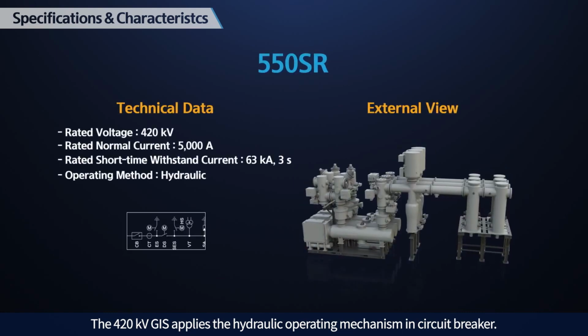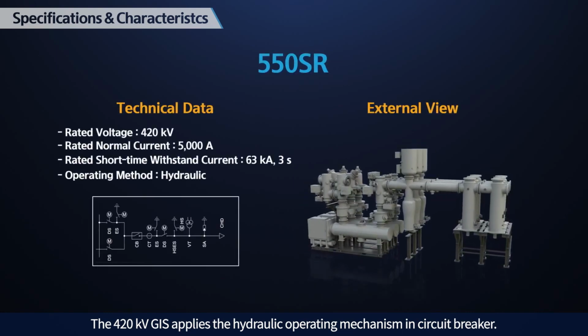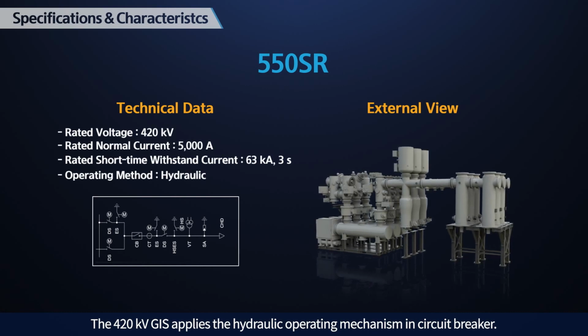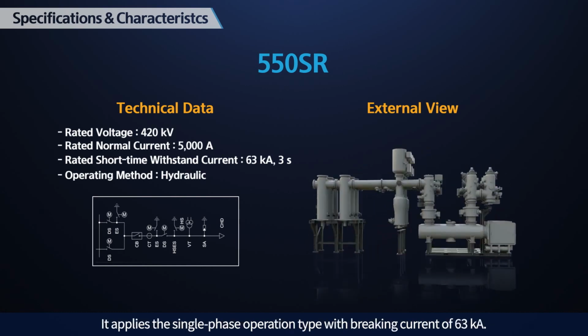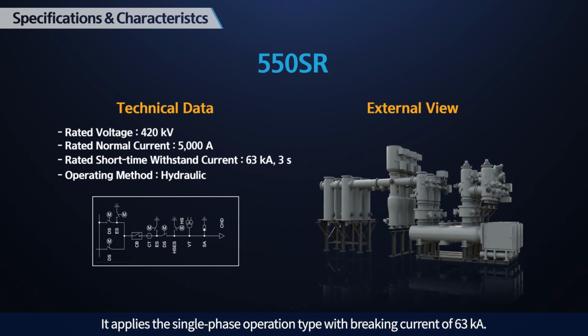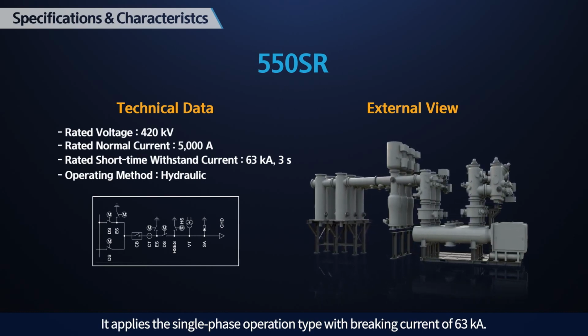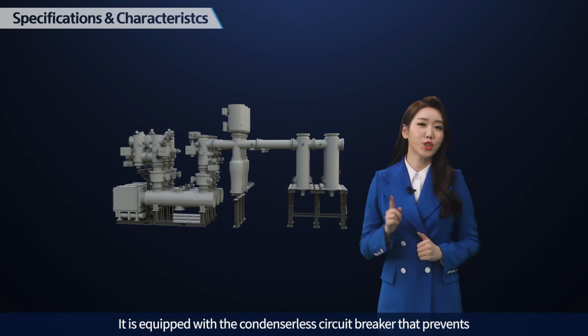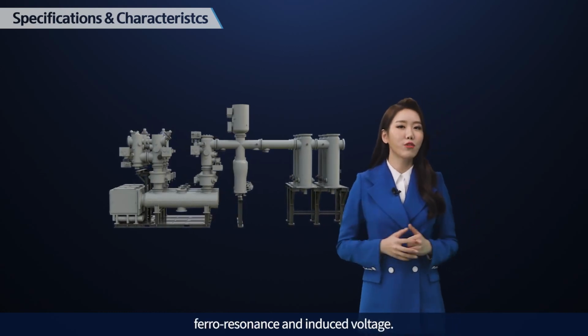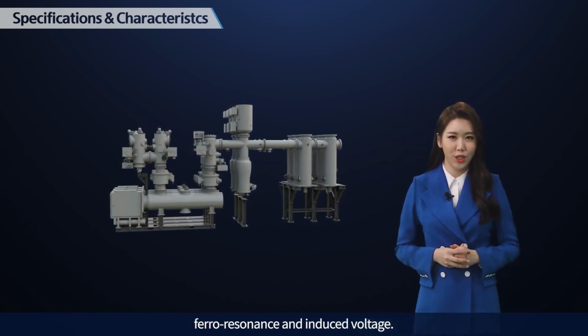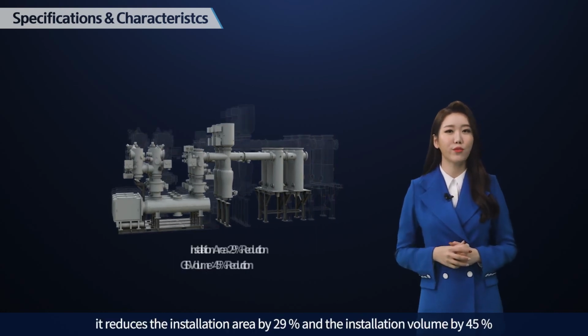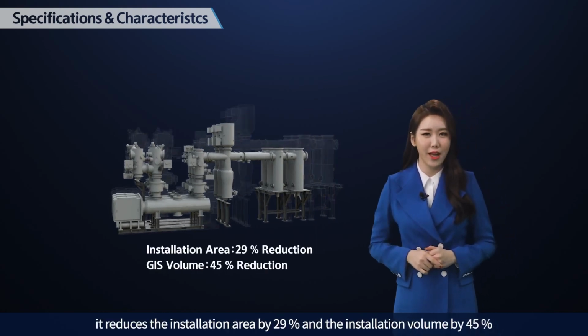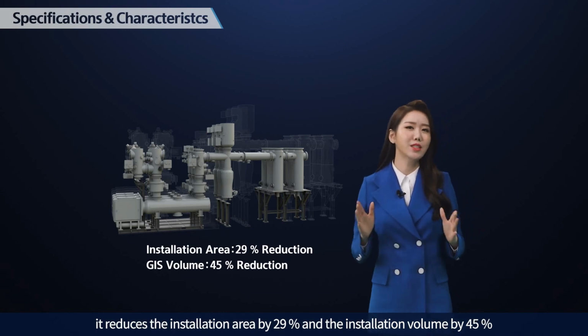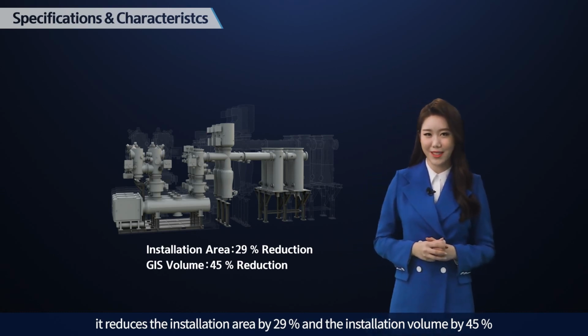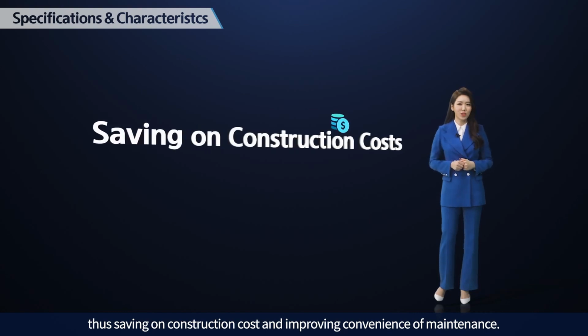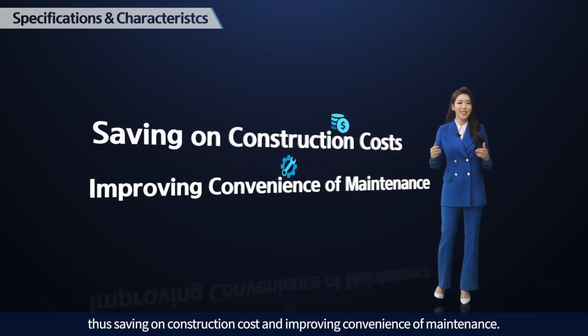The 420 kV GIS applies the hydraulic operating mechanism in circuit breaker. It applies the single-phase operation type with breaking current of 63 kA. It's equipped with a condenserless circuit breaker that prevents ferroresonance and induced voltage. Compared to existing products, it reduces the installation area by 29% and the installation volume by 45%, thus saving on construction cost and improving convenience of maintenance.